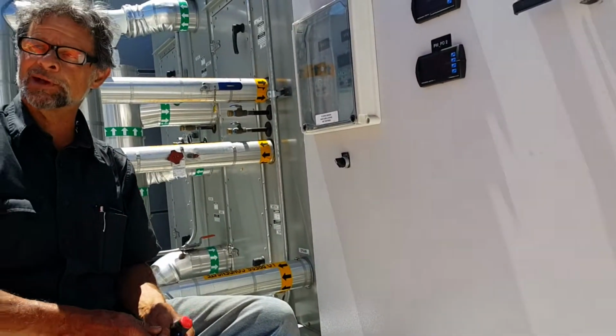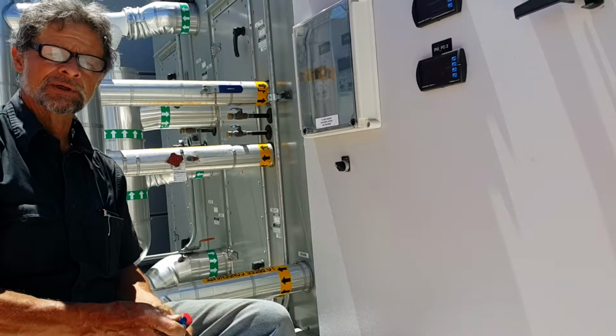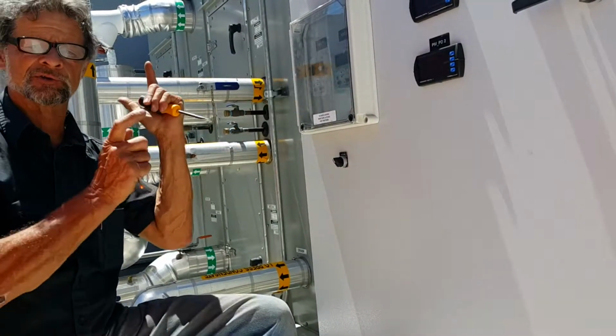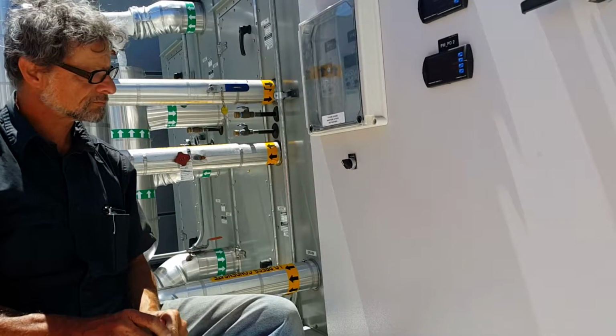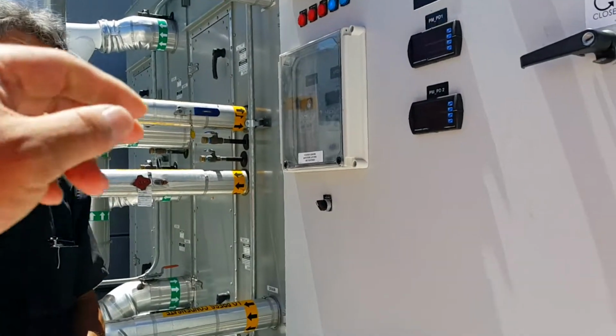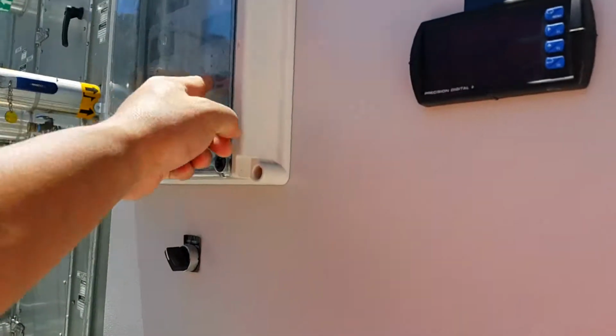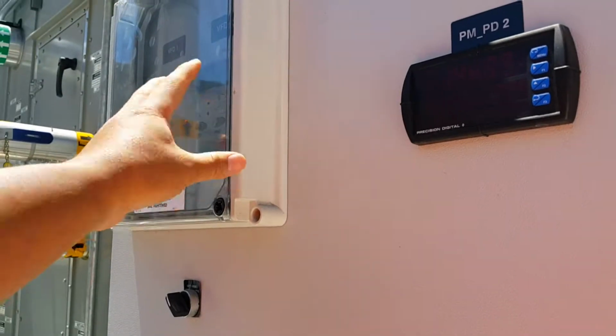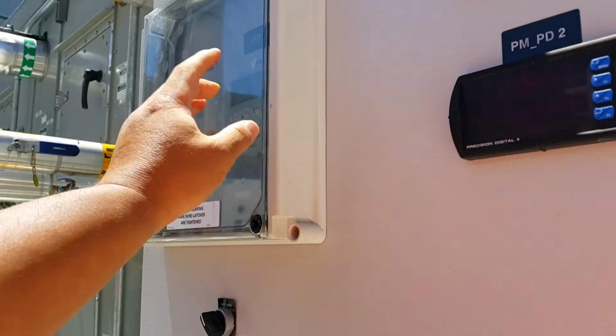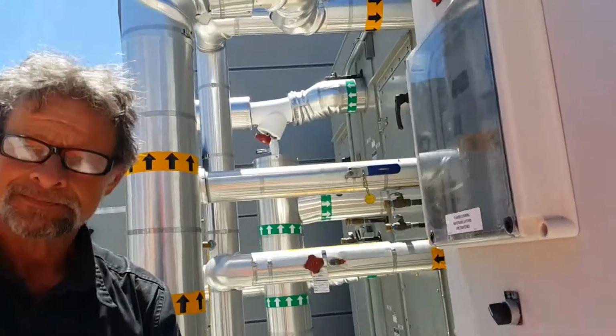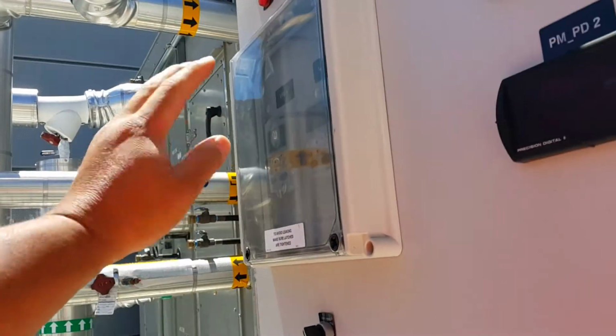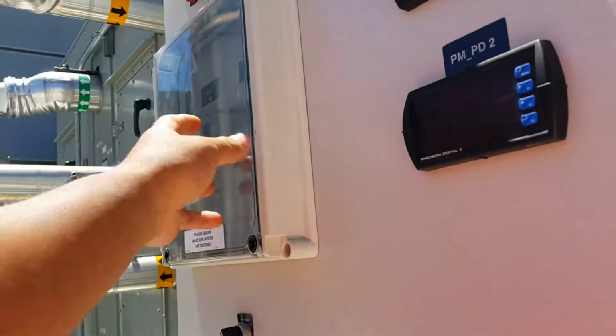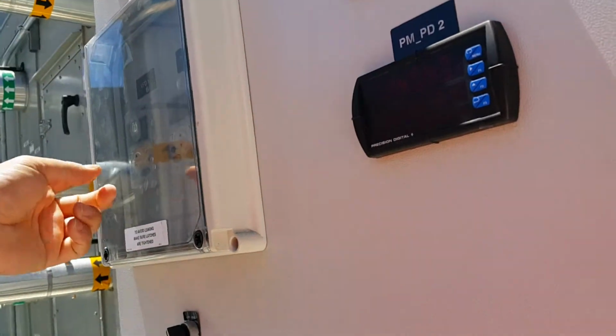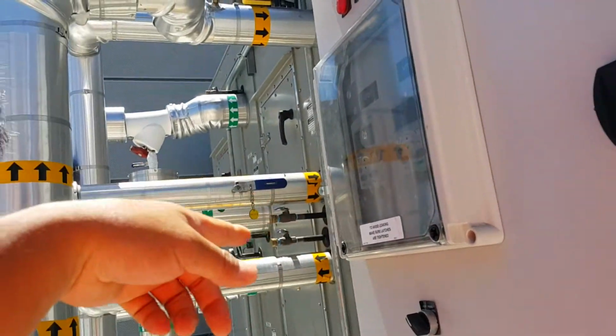Take that panel display, so you can pull the cable; it loses communication with this because of the alarm. Hey, where are you going to go? Now this has two VFDs and these two heads, and they store the memory of the settings, right? Now are they interchangeable? Yes. Okay. So if one goes down or loses something and we have to replace it, we could just get the information off of here and download it into that one, right?